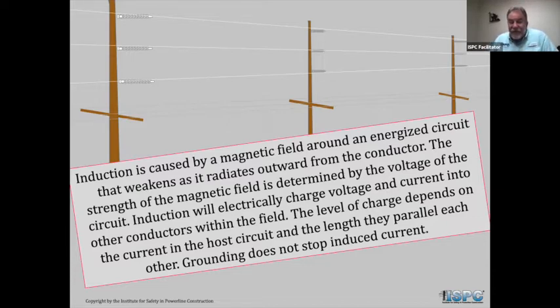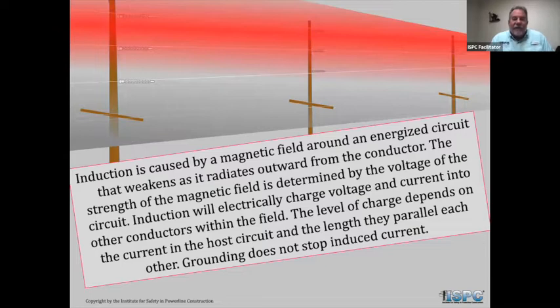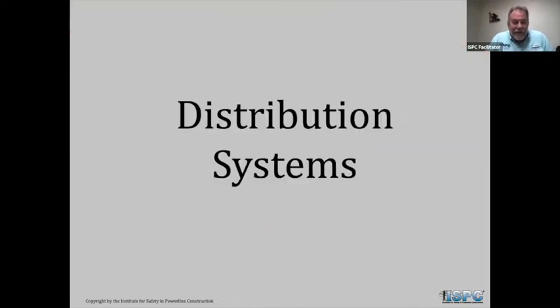All right, so induction is caused by the magnetic field around the energized circuit. It weakens as it radiates outward from the conductor. So at 18 inches from the conductor, you may get a charge. And you can feel it. At 24 inches, you don't feel anything. So it drops off as it goes out. And we usually spend a lot of time trying to get the folks to understand how that works.